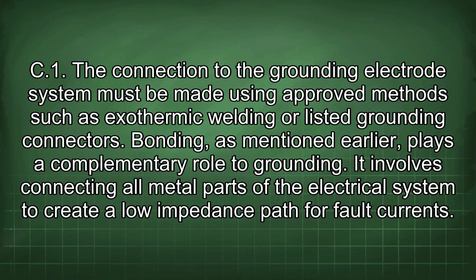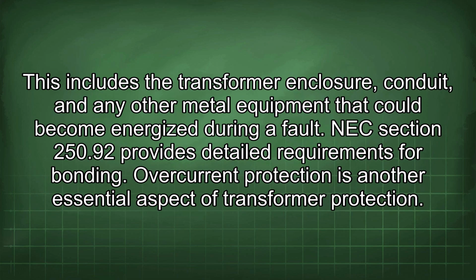It involves connecting all metal parts of the electrical system to create a low impedance path for fault currents. This includes the transformer enclosure, conduit, and any other metal equipment that could become energized during a fault. NEC section 250.92 provides detailed requirements for bonding.